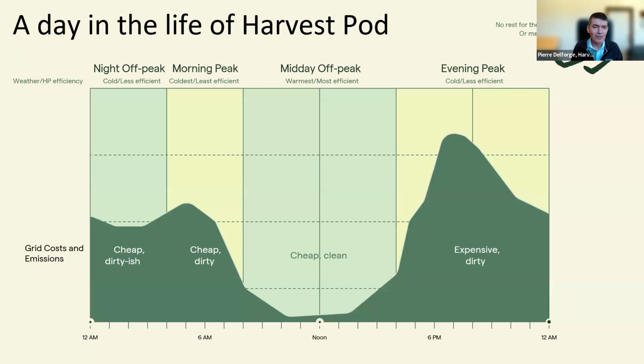So back to the life of the grid operator, and just how does this thermal battery work? So in the middle of the day, again, lots of cheap and clean electricity. So that's when the thermal battery is going to be charged. The heat pump is going to charge the thermal battery. Then in the evening, we're going to discharge the thermal battery to provide heat and hot water without running the heat pump as long as we have enough storage left.